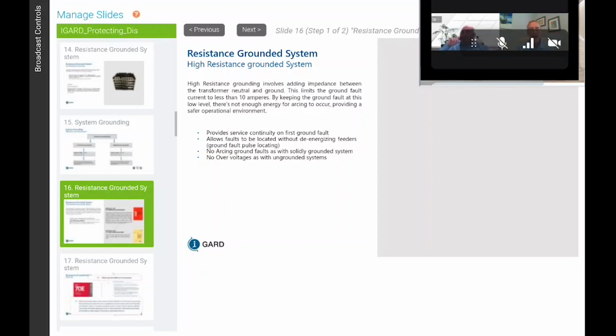All right, here's the last question for you, then we'll wrap things up. When would you use a resistor versus a reactor for neutral grounding? Okay, that's a great question, and I get this from my salespeople all the time. The difference between a resistor and a reactor, there's a couple of things. Reactors are really good when it comes to high current. So you don't want to limit the fault current to a couple of thousand amps if you're interfacing with a utility, and if you want to observe the X over R ratio of your system.